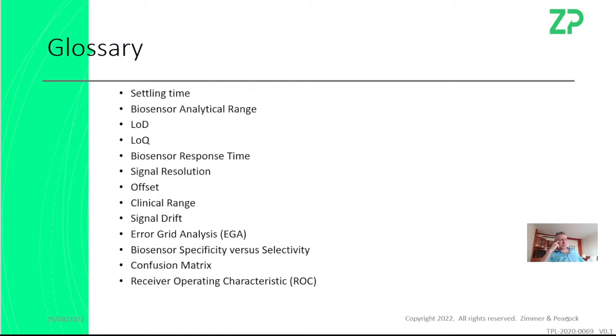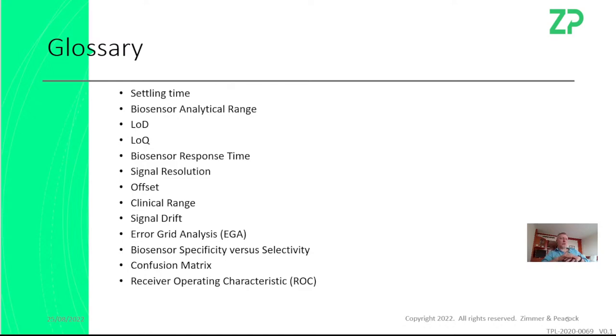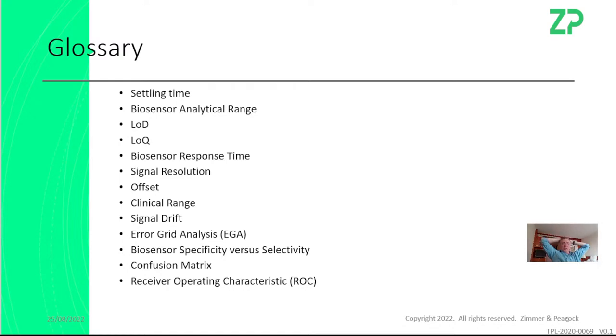We've got a case where the signal was expected to be between zero and 10 micromolar, but most of the time the concentration is actually one micromolar. So we developed a sensor to work between zero and ten, and 90% of the cases are at one — it's a real overkill. If you develop an algorithm that works really well over a range of zero to ten but most of the numbers are at one, you would have been better off to develop and characterize more in the zero to one range.